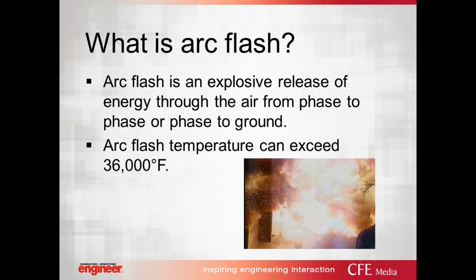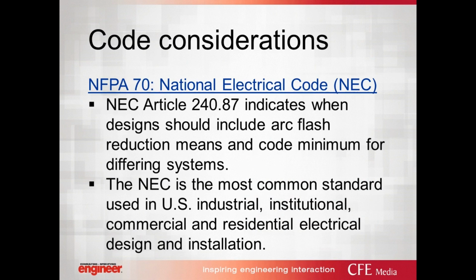Now, our code considerations. Obviously, NFPA 70, the NEC, is one of the premier considerations. Article 240.87 indicates when designs should include arc flash reduction means and what the code minimum is for differing systems. Anytime there is a high continuous current trip setting for the overcurrent protection device installed in a breaker, and it is at or above, or can be adjusted to above, 1200 amps, it is going to be required to have arc flash mitigation. The NEC is the single most common standard used in the U.S.